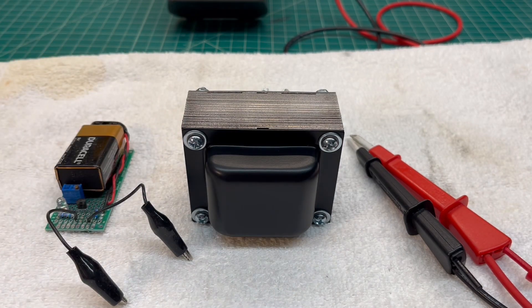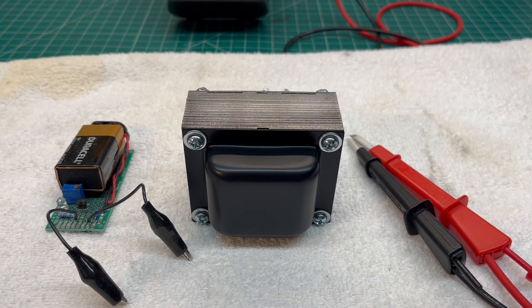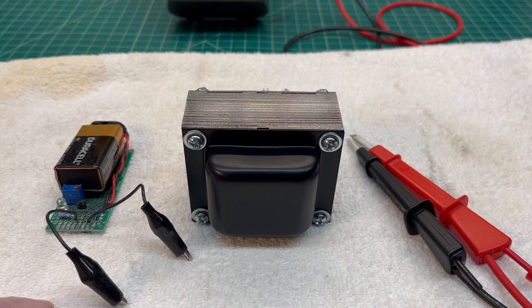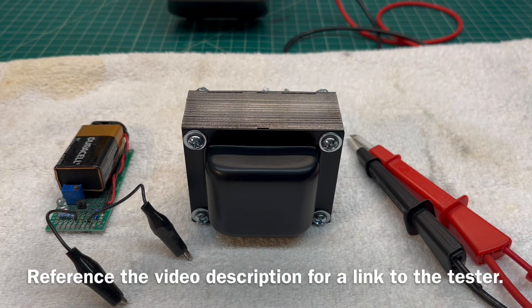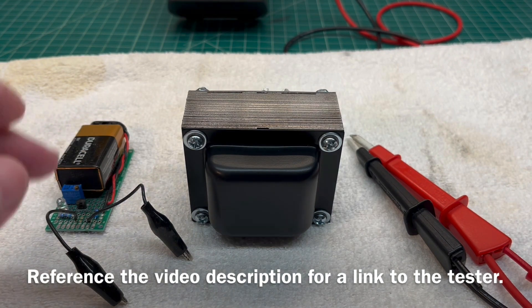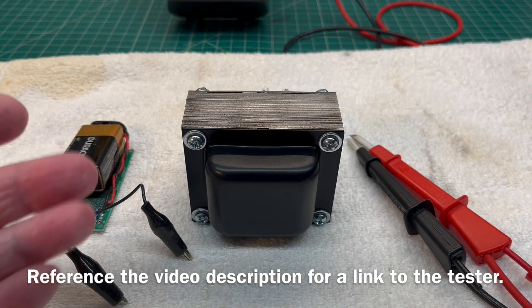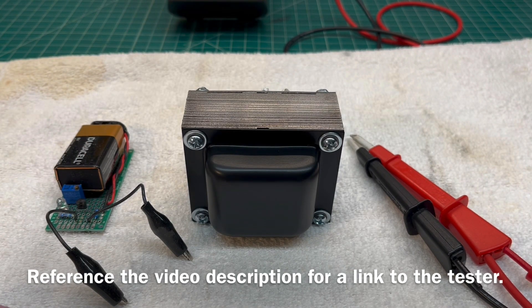New hardware is in place and I've already done some preliminary DC checks. Everything looks good. Let's look at the DC resistance using this little circuit that I built some time back and see if we've got any leakage from any of the connection points back to the housing itself or across any other windings. This will actually read in the mega ohms.